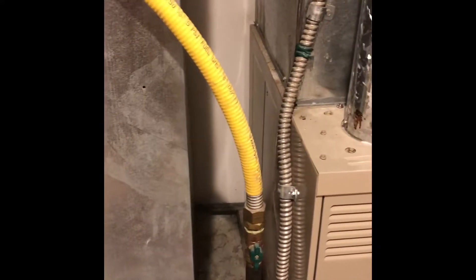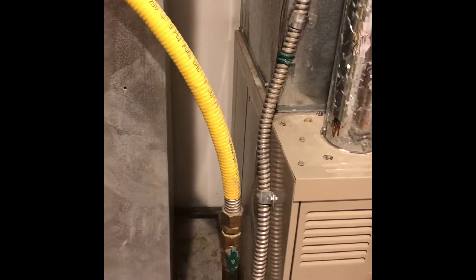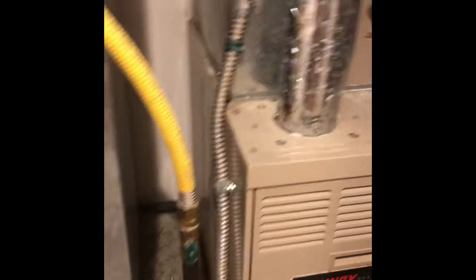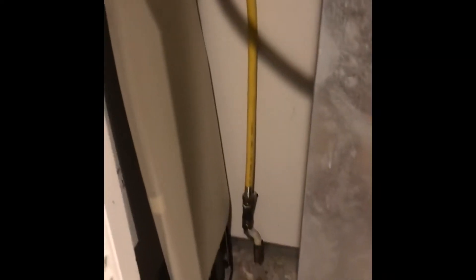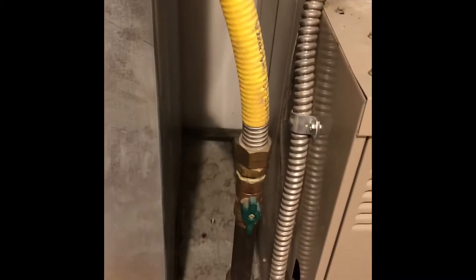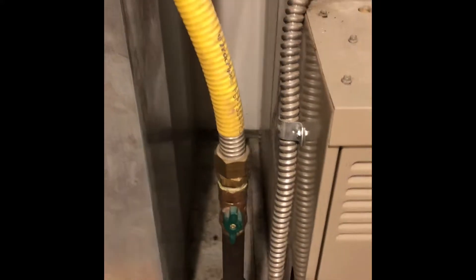Our gas line — we're going to possibly have to change it around because it doesn't look like it's bonded up here anyway. We have flex line TracPipe that runs from down here on the floor up to the furnace. There is a shut-off valve, but they cut too much of the wrapping off of the flex line, so it wouldn't be properly insulated.